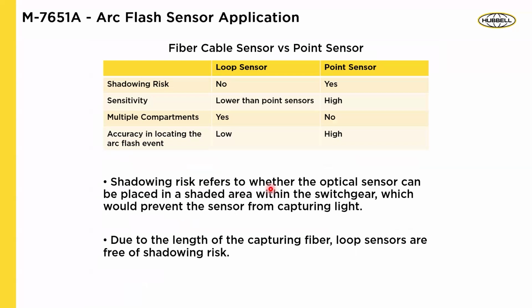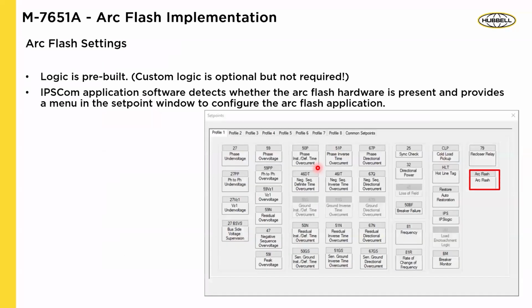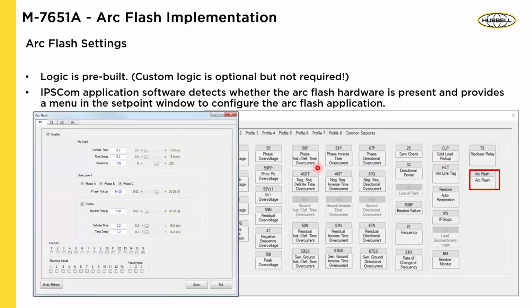And then there's some advantages and disadvantages you see of having a loop sensor versus a point sensor. There are strategies on how you best optimize that. Okay, so logic is pre-built for arc flash, so you don't have to do it by yourself. And then there's the settings for the arc light. Then you could do an overcurrent supervision on different phases. And it's very simple how you program it. And we typically keep it very sensitive because you are putting it in a darker environment. So any light that comes in is detected right away, and you want the highest speed possible.